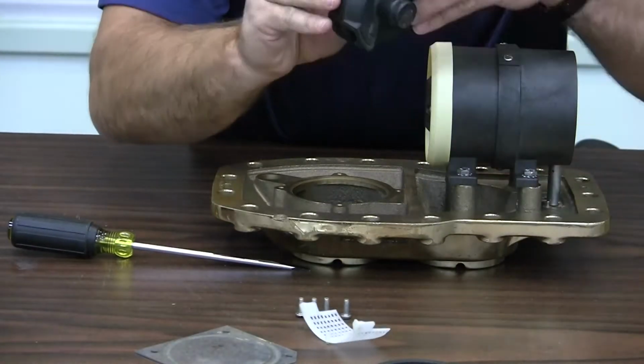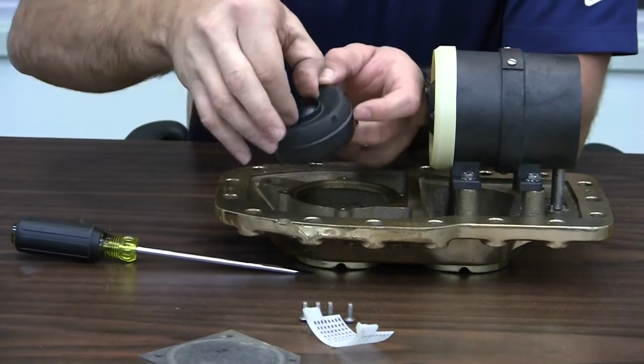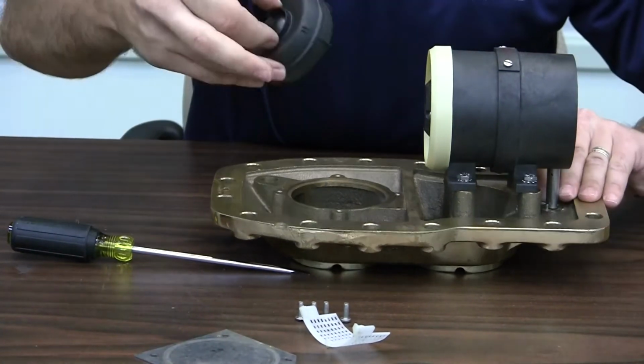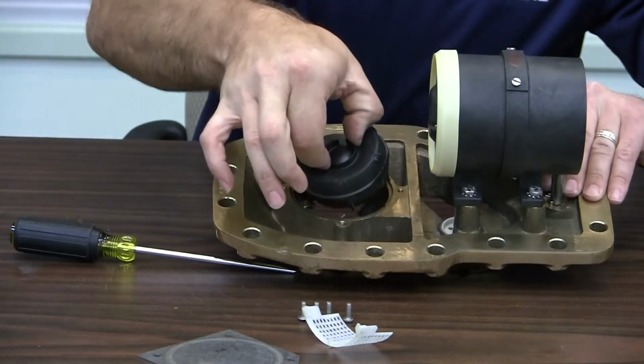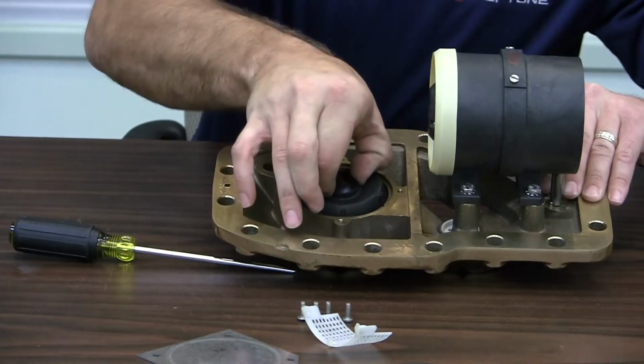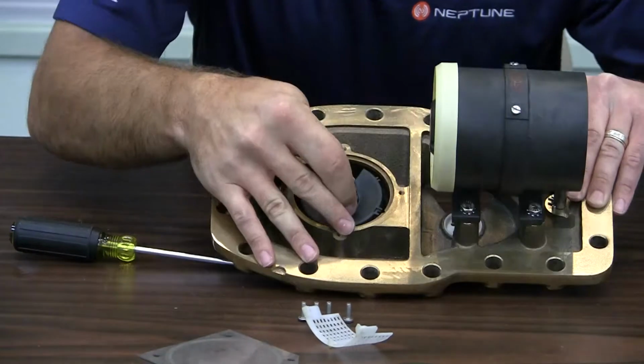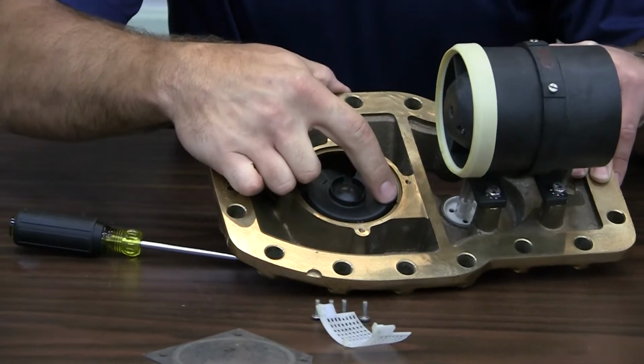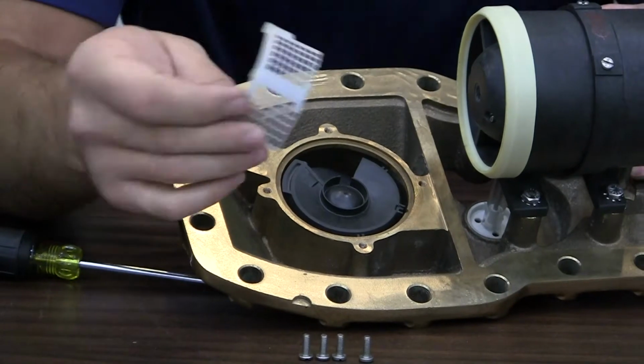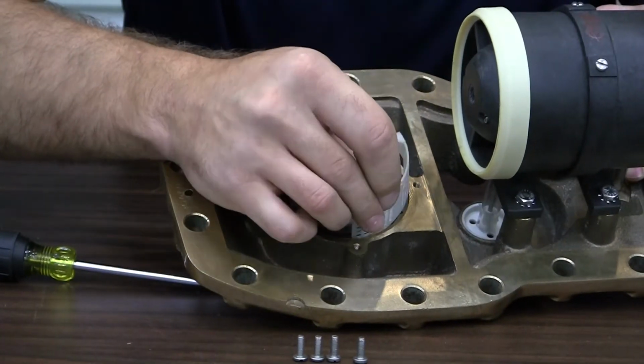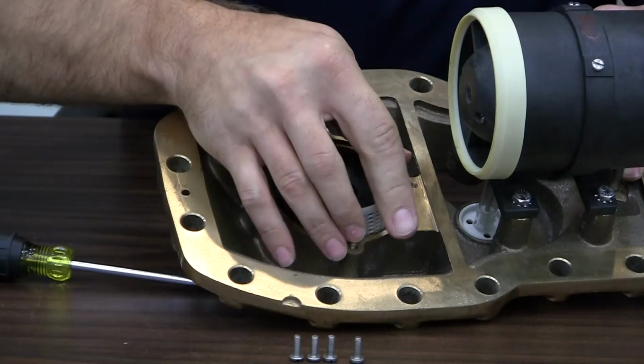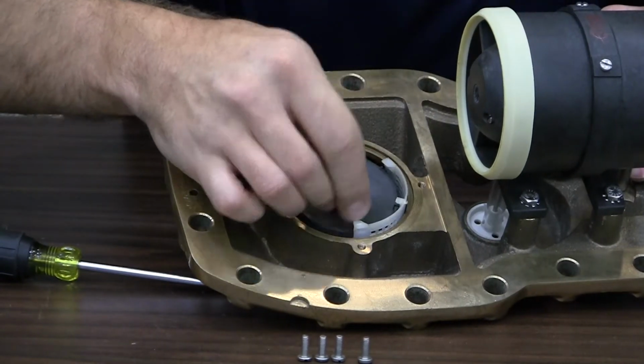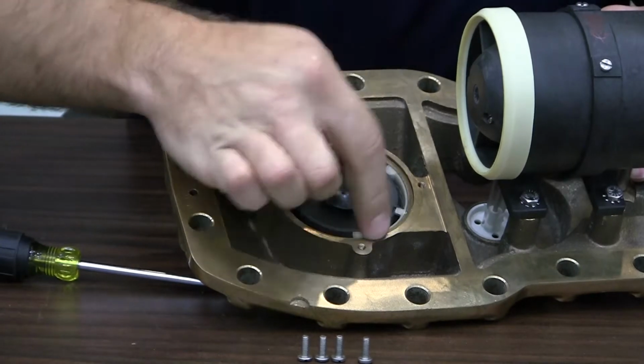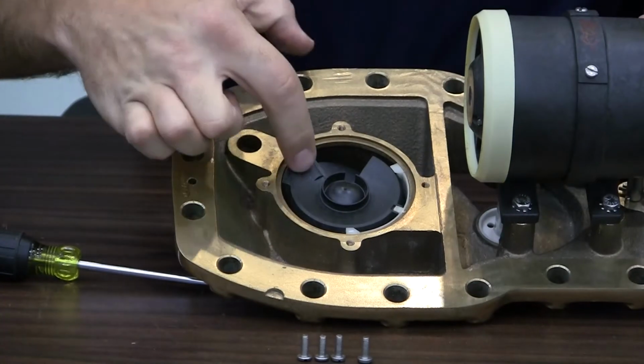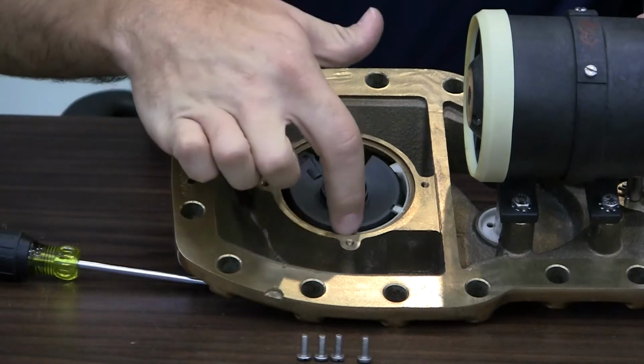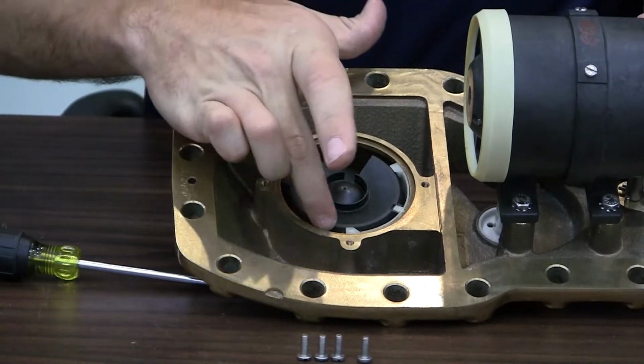So to put that back in, we're going to take the chamber. You can grab it from the bottom of that ring, placing that sealing surface towards that machined area. Once you have it in, you want to align the feature on the chamber with that half moon and slide your strainer in to lock it in. Once the chamber is locked in, the gasket should be firmly against this side of the cover, and the strainer should be flush with the top of that groove.